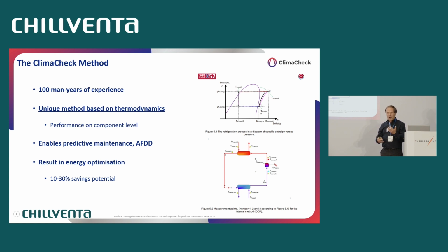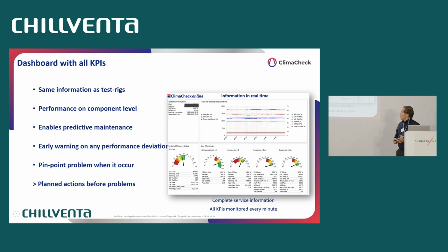It's interesting because it's large industrial plants and so on. But for most systems, you can make a very simple assumption on heat losses and get within a few percent of the COP, which is better accuracy than if you use flow-based measurements on the water side. And on the air side, it's almost impossible in the field to measure flows and humidities in a dynamic system. So when we apply the thermodynamics, I showed you this basic process, but of course you can do it for multi-stage systems, economizers, and CO2 booster systems. The thermodynamics is valid for everything we do.